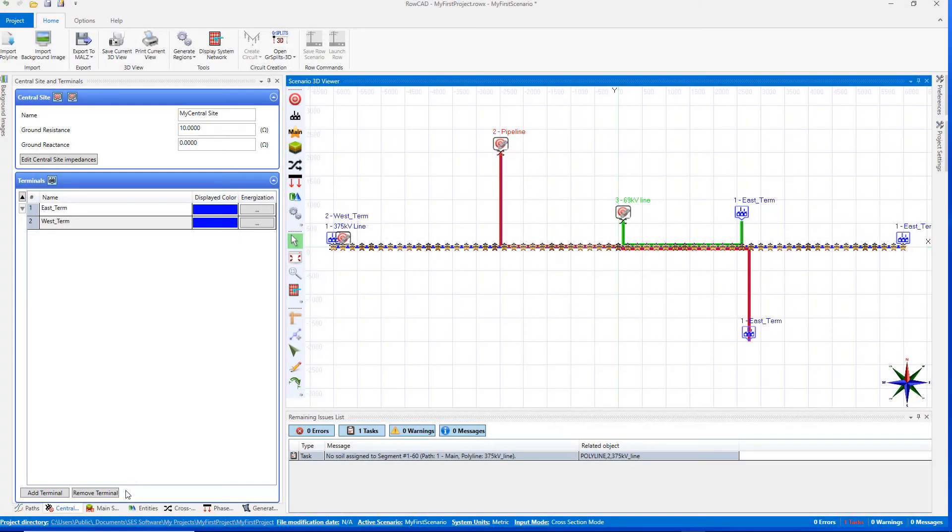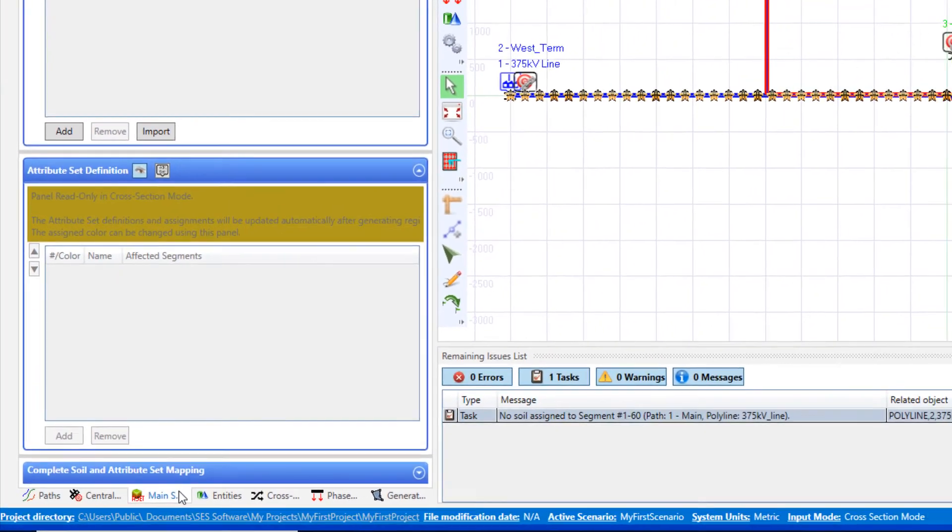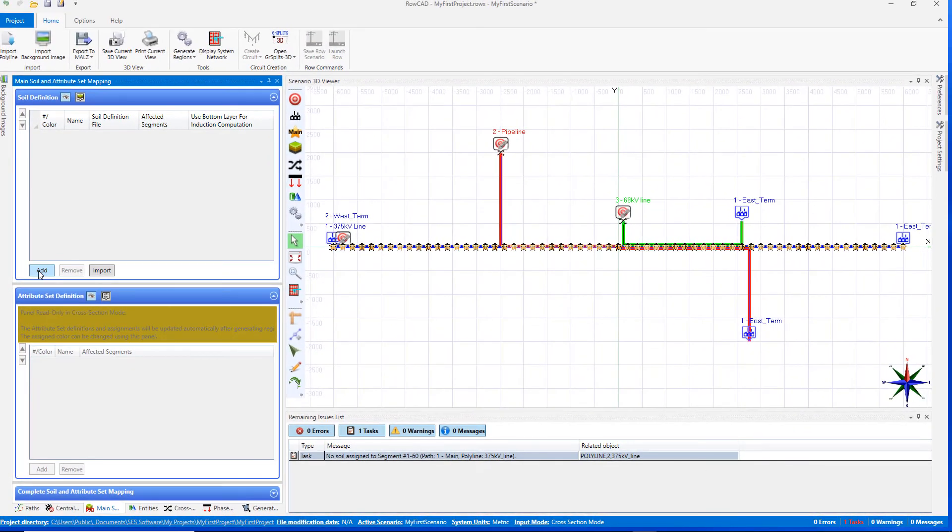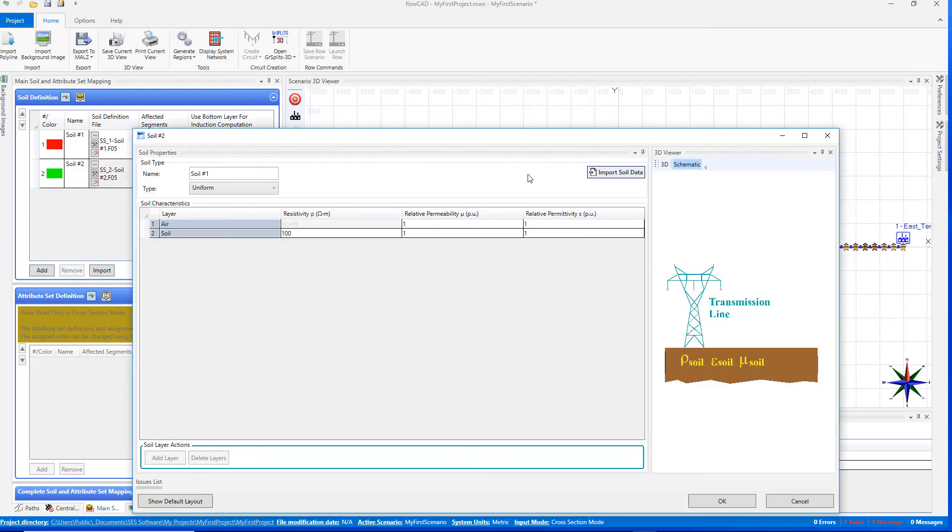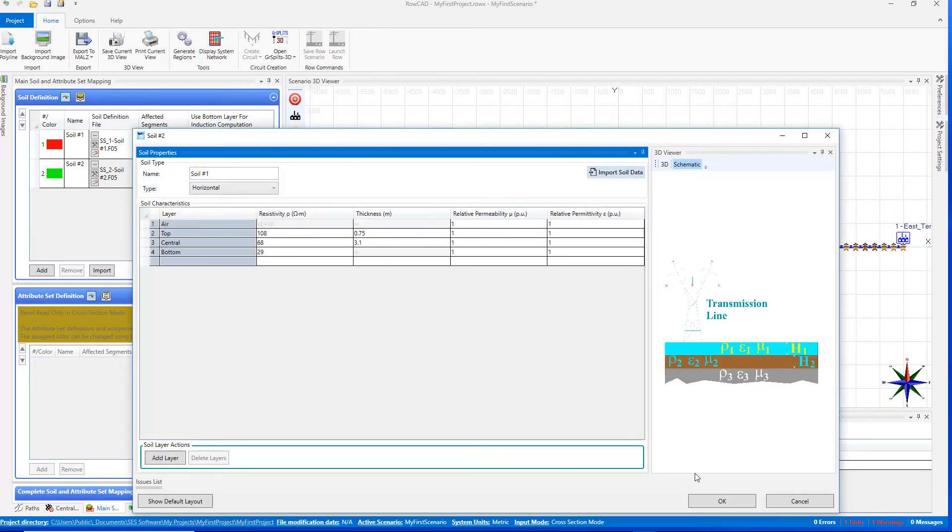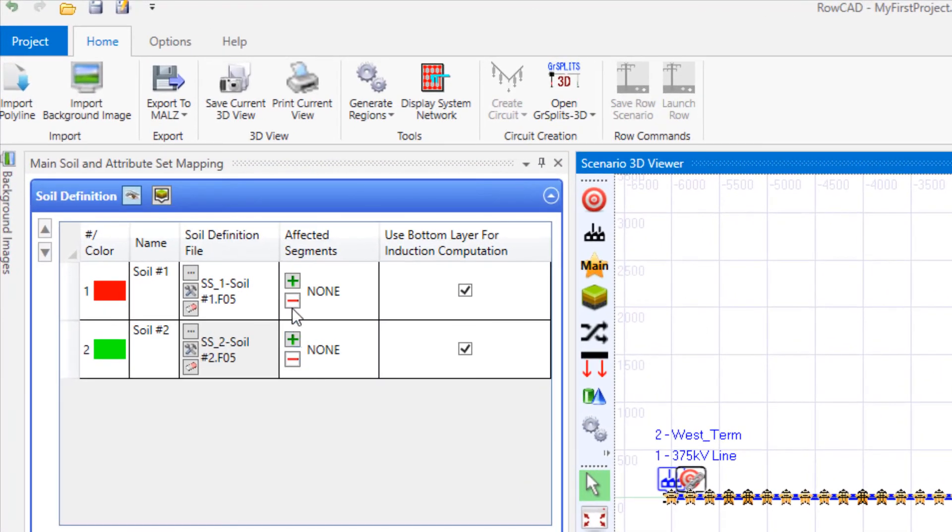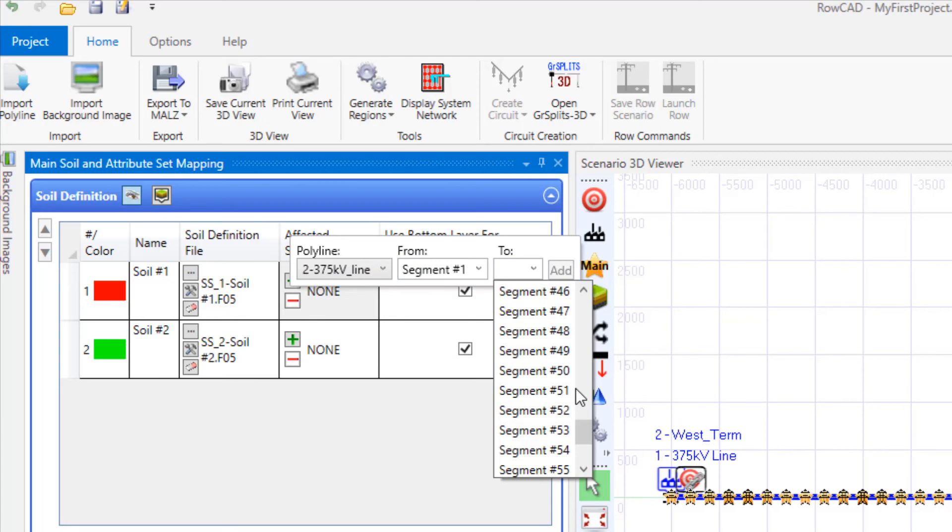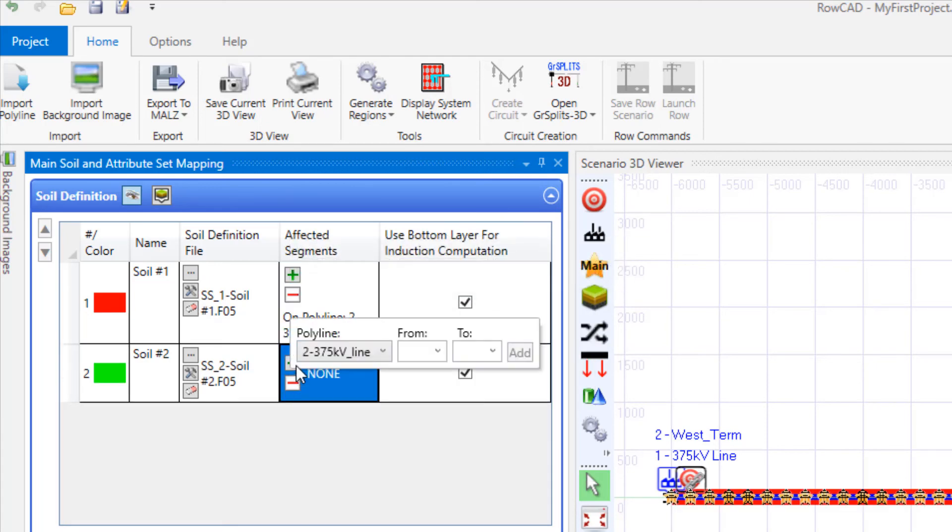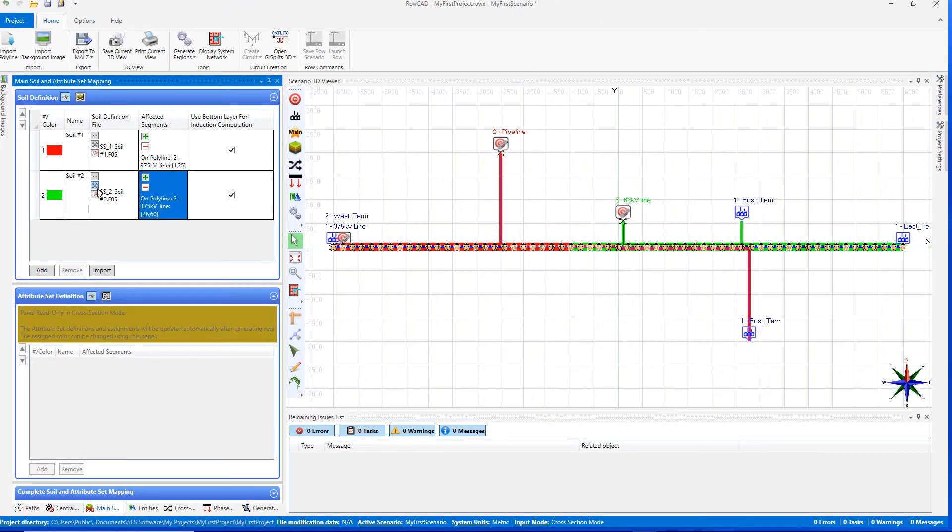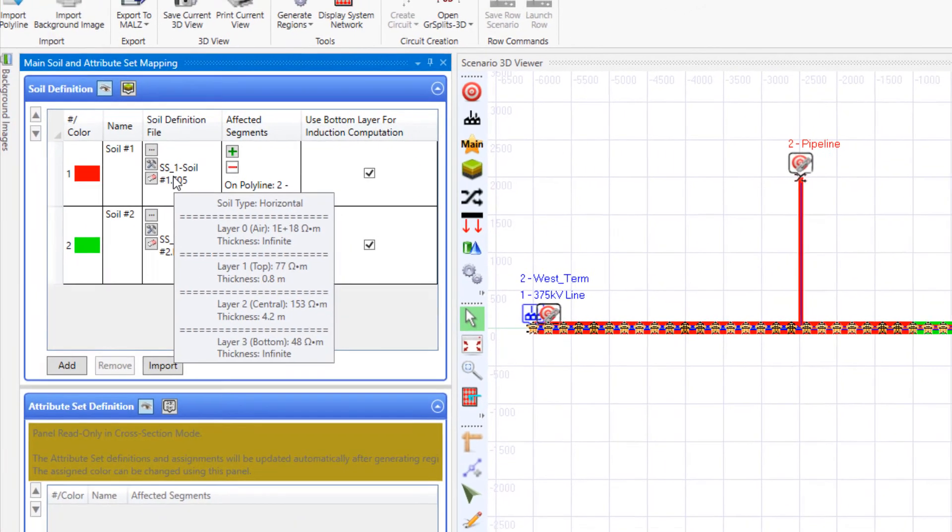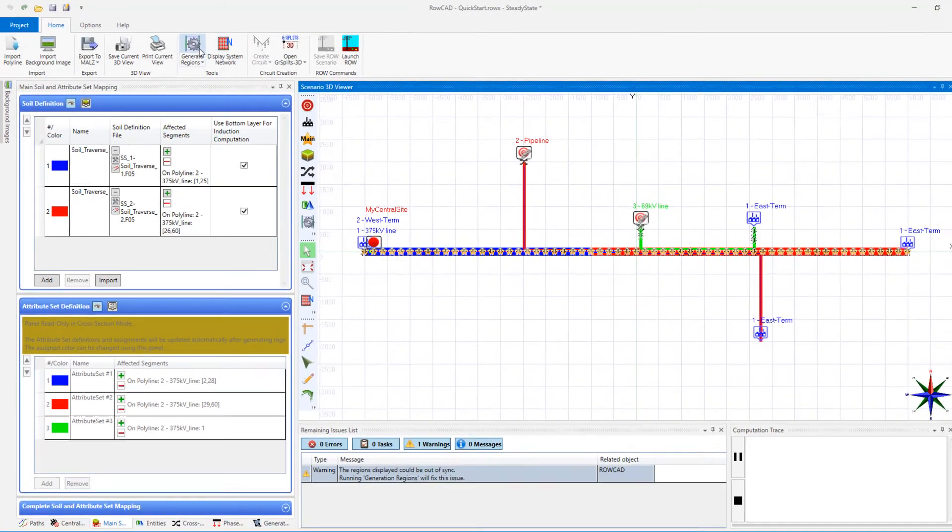Soil structures need to be assigned along the right-of-way. The assignment is made to the main path. Navigate to the main soil and attribute set mapping panel. Click twice on the add button under the soil definition group to add two soil structures. You can either import an already defined soil structure, or you can specify the soil from a RESAP file. Assign the soil structures to the polylines forming the main path using the plus button. By hovering over soil definition file, a preview window shows the defined soil structure.